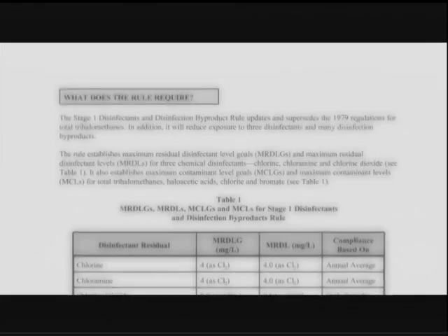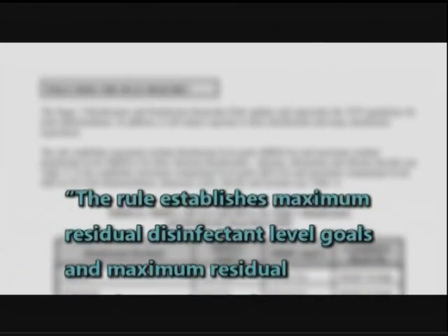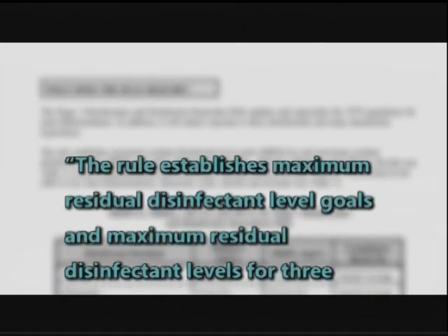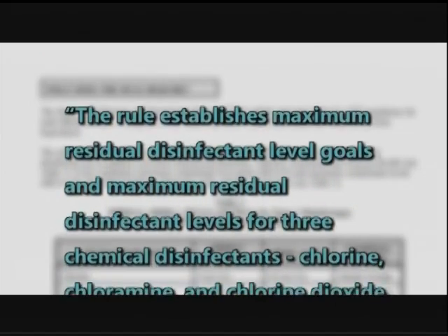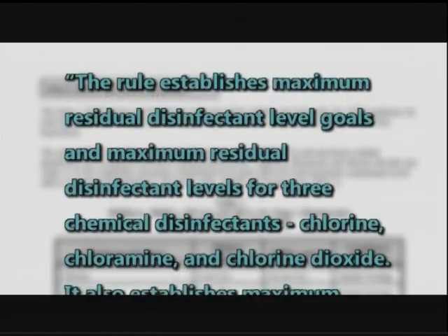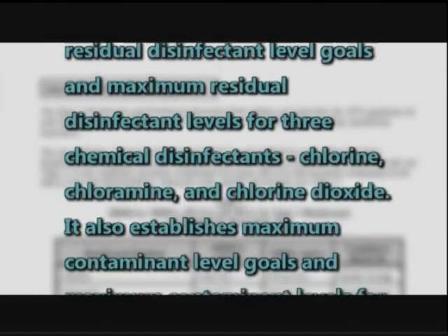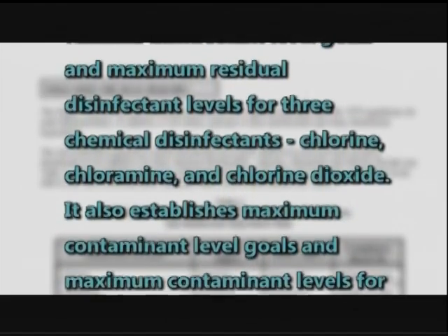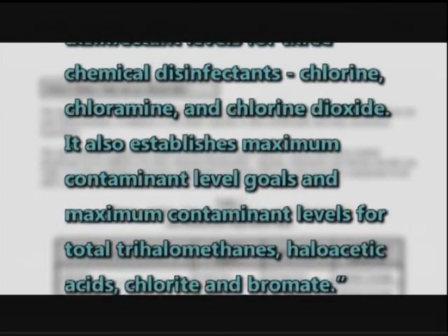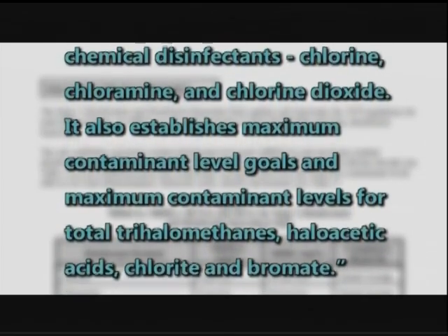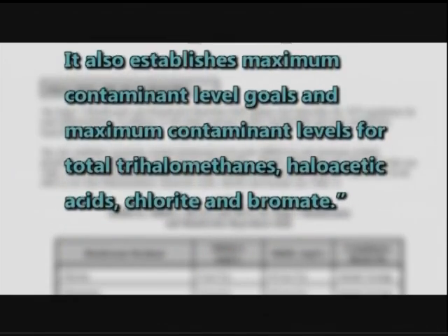According to the EPA, the Rule establishes maximum residual disinfectant level goals and maximum residual disinfectant levels for three chemical disinfectants: chlorine, chloramine, and chlorine dioxide. It also establishes maximum contaminant level goals and maximum contaminant levels for total trihalomethanes, haloacetic acids, chlorite, and bromate.